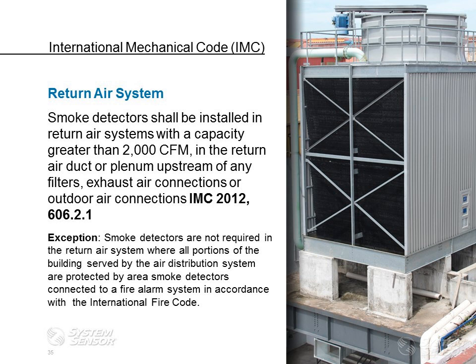So, the International Mechanical Code. What the International Mechanical Code states is that in the return air system, smoke detectors shall be installed in return air systems with a capacity greater than 2,000 CFM, in the return air duct or plenum upstream of any filters, exhaust air connection, or outdoor air connections. There is an exception. Smoke detectors are not required in a return air system where all portions of the building served by the air distribution system are protected by area smoke detectors connected to a fire alarm system in accordance with the International Fire Code.